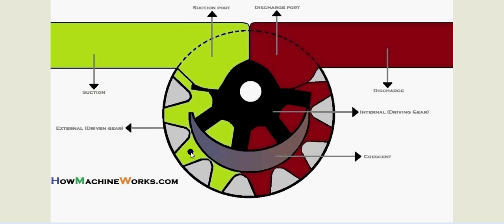trapped between the gears. Like this, you can see the green color - the oil is getting trapped over here between the gears and the crescent, and it has been carried through this gap between the gears. And at the discharge, it has been pushed outside.